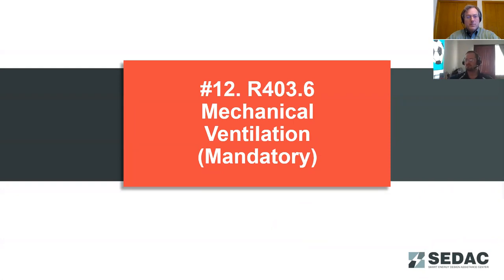We did have a question about natural ventilation reductions with regard to system sizing. Does that mean opening windows? Don't we want to rely on mechanical ventilation in residential as little as possible? The thing with natural ventilation is it's inconsistent. It relies a lot on wind direction and wind speed. And for large components of the year, it's too hot or too cold to leave a window open and rely on natural ventilation. So you have to have a mechanical system that's designed to mechanically ventilate during those times when you can't bring in natural ventilation. And so that's why systems are designed and sized now based on that mechanical ventilation requirement. Although yes, when it's temperate enough outside, we would like to see people relying on free cooling and natural ventilation.